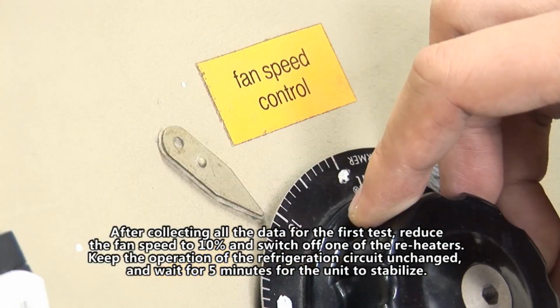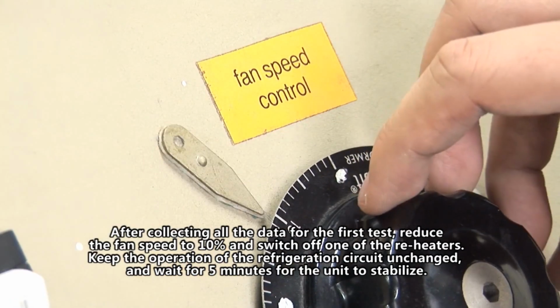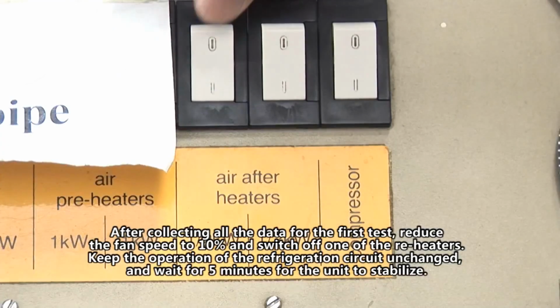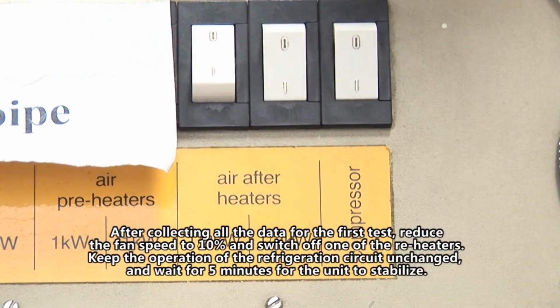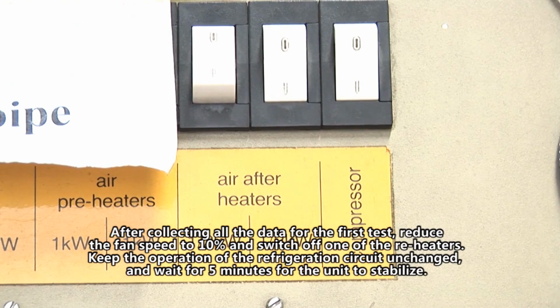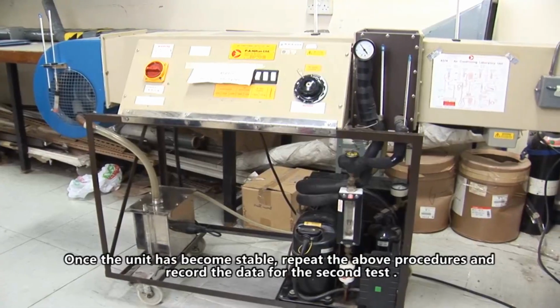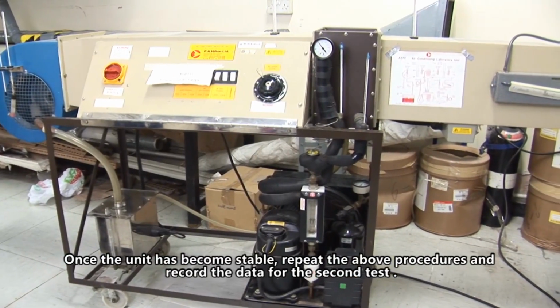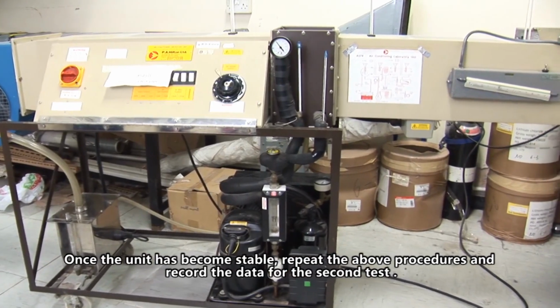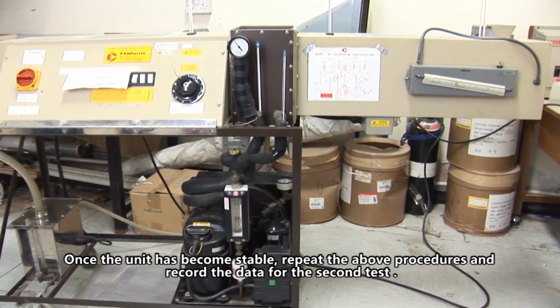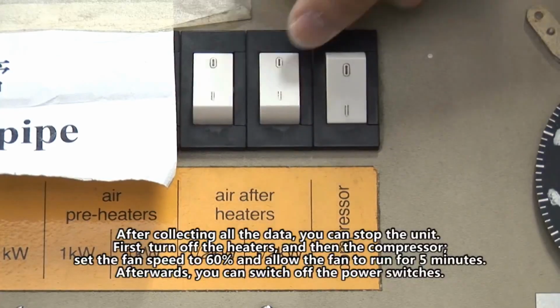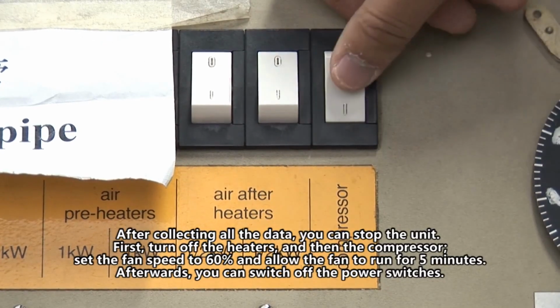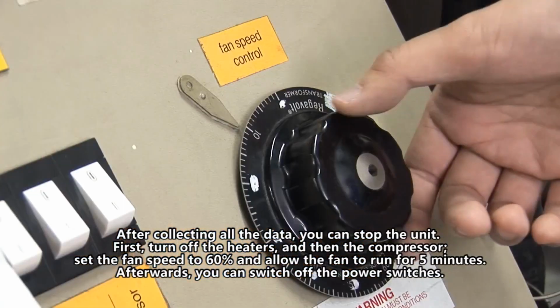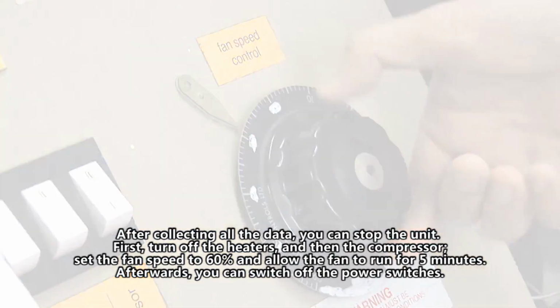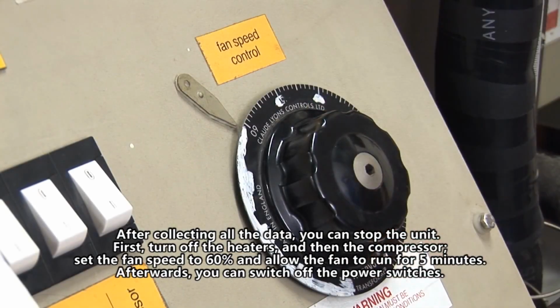After collecting all the data for the first test, reduce the fan speed to 10% and switch off one of the reheaters. Keep the operation of the refrigeration circuit unchanged and wait for 5 minutes for the unit to stabilise. Once the unit has become stable, repeat the above procedures and record the data for the second test. After collecting all the data, you can stop the unit.